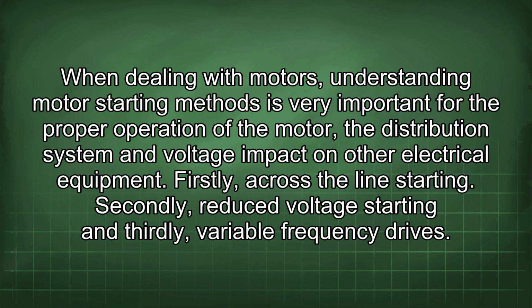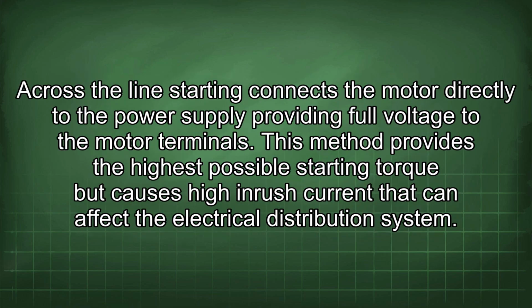When dealing with motors, understanding motor starting methods is very important for the proper operation of the motor, the distribution system, and voltage impact on other electrical equipment. Firstly, across the line starting. Secondly, reduced voltage starting, and thirdly, variable frequency drives. Across the line starting connects the motor directly to the power supply, providing full voltage to the motor terminals. This method provides the highest possible starting torque but causes high inrush current that can affect the electrical distribution system.